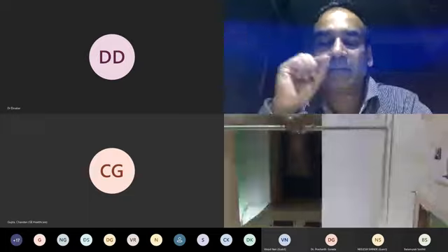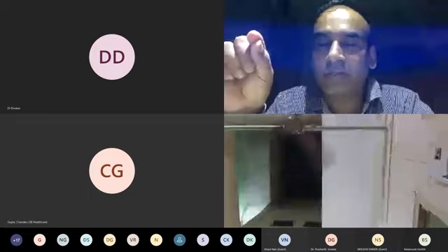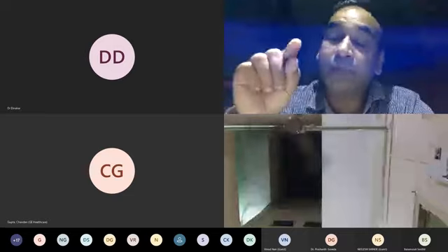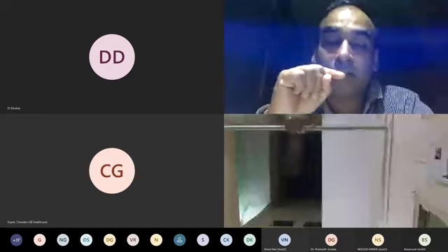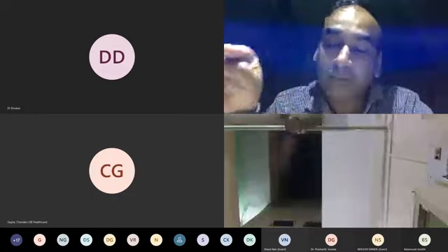There was a lot of sludge in that, and we never knew about the sludge formation. So then we started cleaning the sludge every 3 months. It was difficult to open. Then the infection rate came down. It means the moisturizing aspect of the incubator is not good when compared to Giraffe.